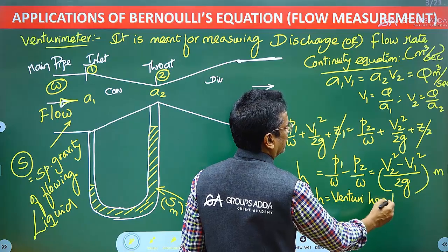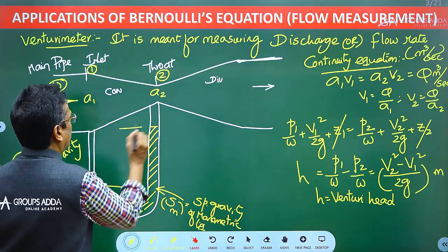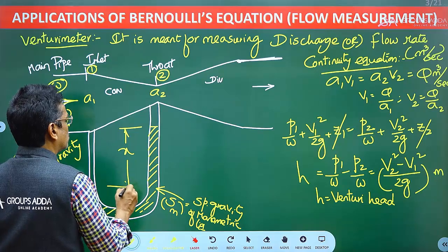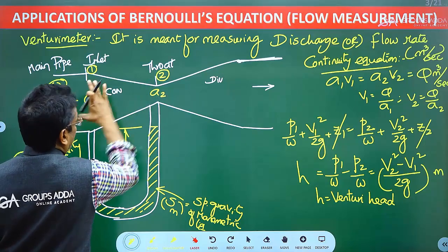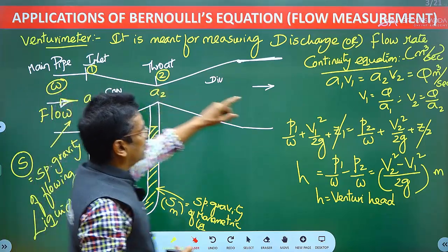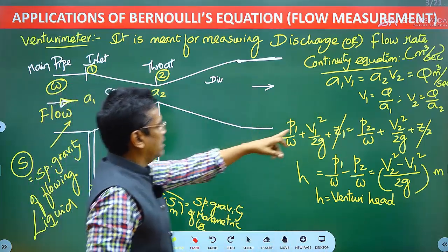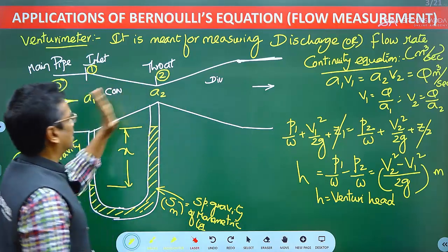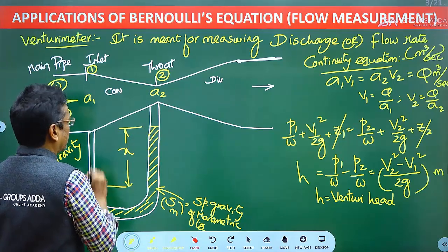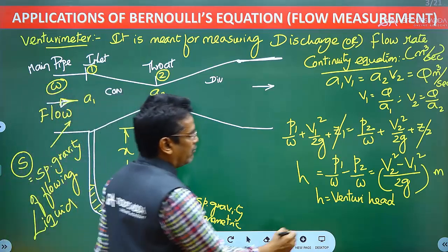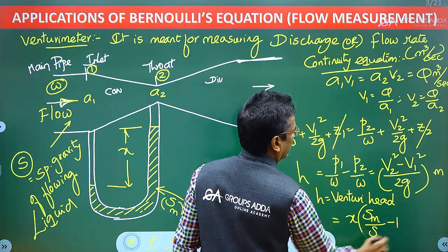H is called the Venturi head, measured in meters. As the area decreases at the throat according to the continuity equation, velocity increases; and according to Bernoulli's equation, the pressure decreases. This pressure difference is reflected in the manometric liquid levels. The Venturi head H is given by X times (SM/S − 1), where X is the difference in manometric liquid levels, SM is the specific gravity of the manometric liquid, and S is the specific gravity of the flowing liquid.